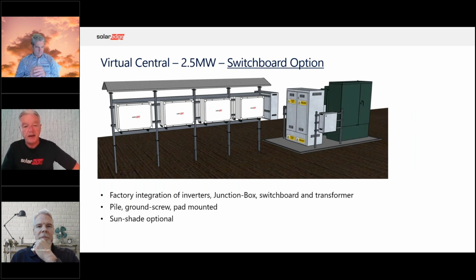Here you see the 2.5 megawatt option. This is the switchboard option. So it has a junction box on the end of the rack, and then you have a switchboard on the power portion of the system, and that's where the overcurrent protection for the inverters is in that switchboard. All of it factory integrated, junction boxes, the switchboard, transformer, all of it factory integrated and pre-wired, and has many different mounting options. Again, you can mount it on piles or ground screws, or even on a concrete pad. It has feet that you can bolt it down.